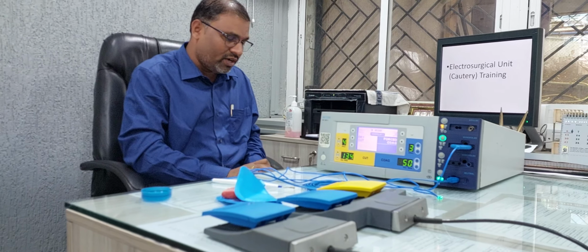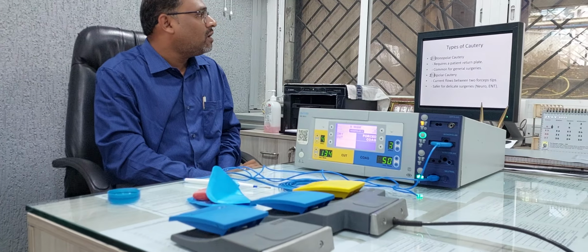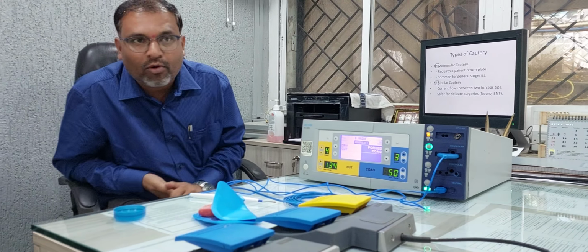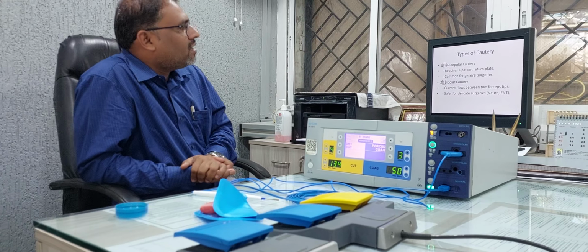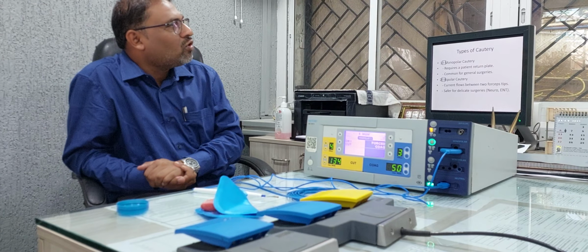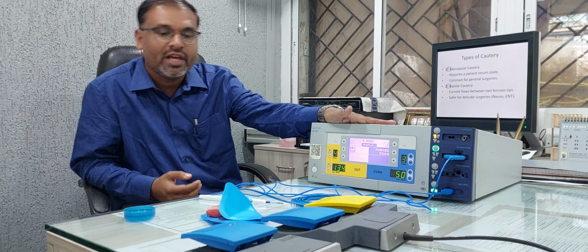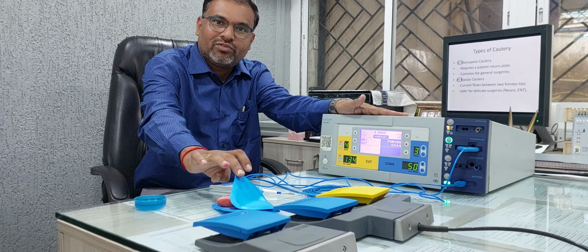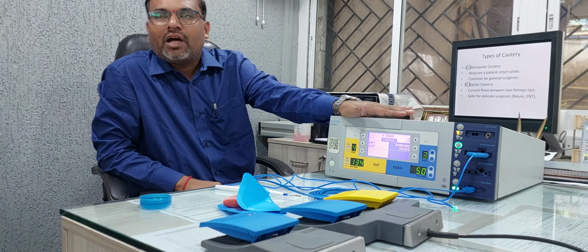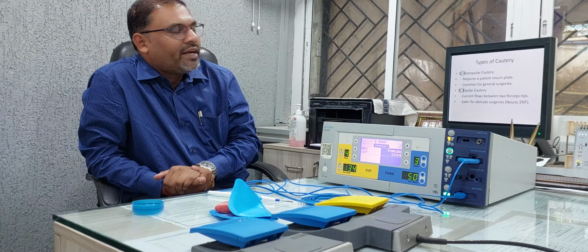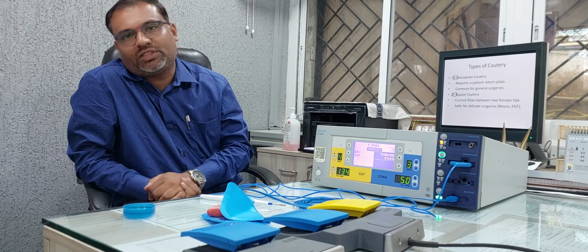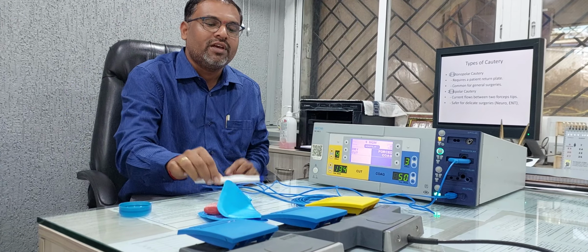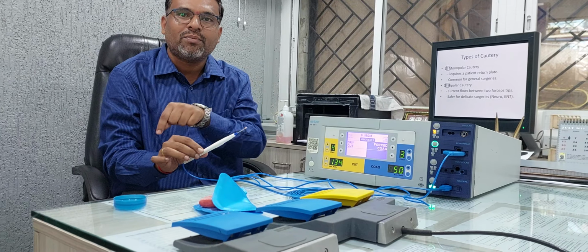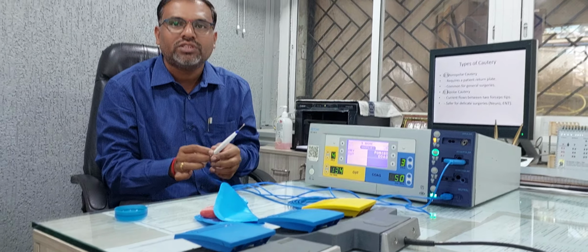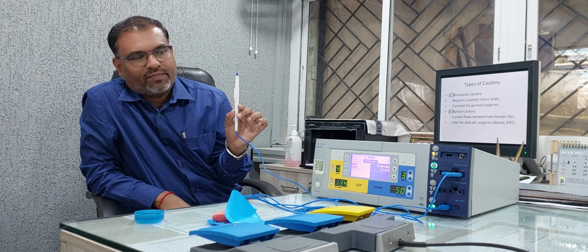Second thing I would like to tell you, basically there are two types of cautery, monopolar cautery and bipolar cautery. So what is monopolar cautery? For the monopolar cautery, you require a patient plate which is connected to the patient, and for the bipolar cautery, the current flows between the forceps only. One is an active needle and one is a passive needle. From the active needle current goes and from the passive needle it comes back, and this is nothing but bipolar, right?